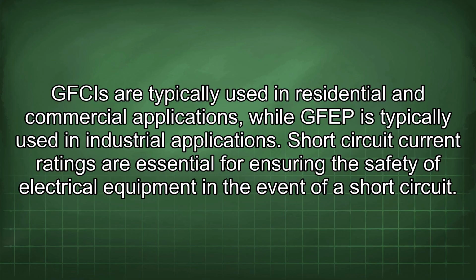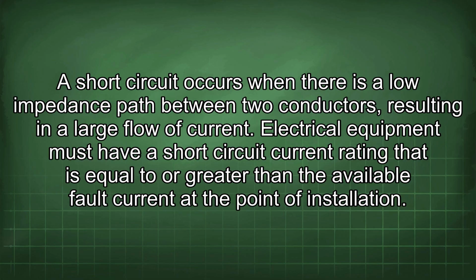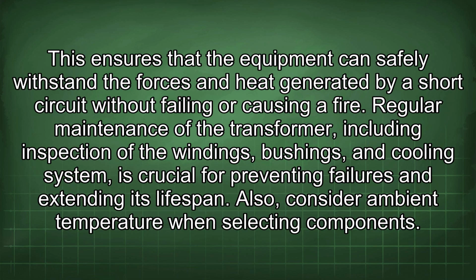Short-circuit current ratings are essential for ensuring the safety of electrical equipment in the event of a short circuit. A short circuit occurs when there is a low impedance path between two conductors, resulting in a large flow of current. Electrical equipment must have a short circuit current rating that is equal to or greater than the available fault current at the point of installation.